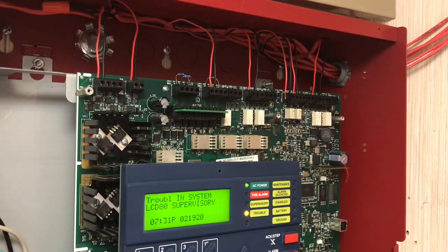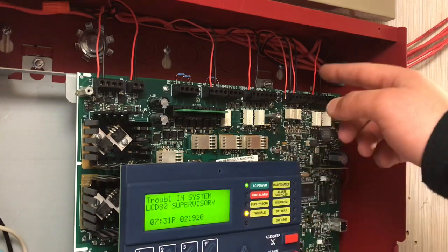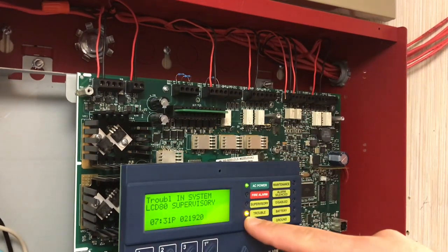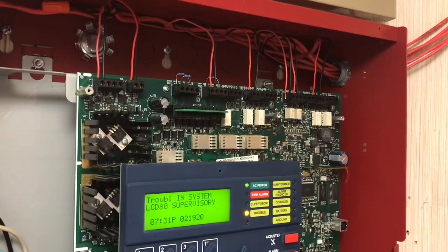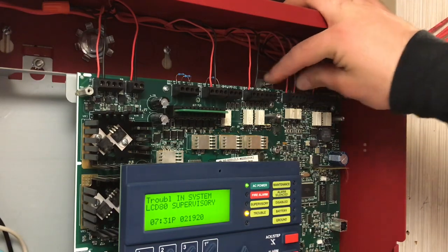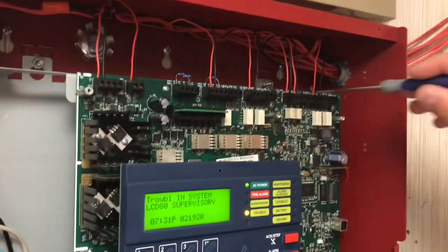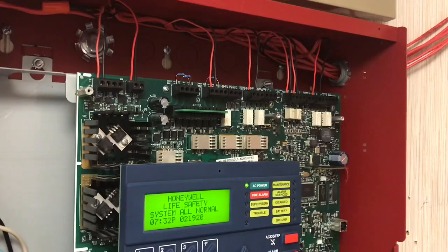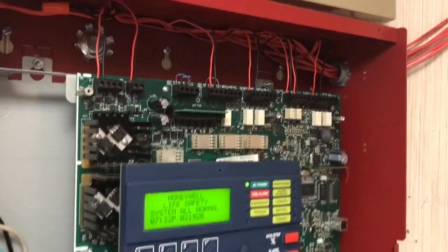If the enunciator says 'communication fault' and you have an LCD-80 Supervisory, you know it's your output wires. If you have an LCD-80 Supervisory trouble on both the enunciator and the panel, you know it's your input wires. That's the difference between the two.